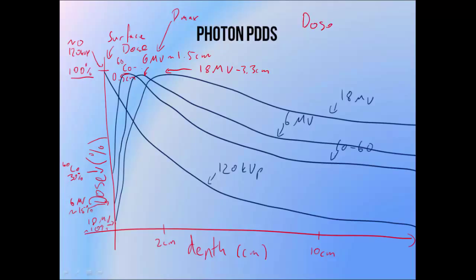The amount of dose delivered at depth also varies with beam energy, which is one of the main reasons why we're interested in treating with higher energy beams. At a depth of 10 cm, a 120 kVp beam only delivers about 21% of its maximum dose. Cobalt-60 delivers about 55%, 6 MV about 67%, and 18 MV about 80%. So if we're interested in treating deep structures whilst delivering a lower dose to structures lying above, a higher energy beam is a good idea.